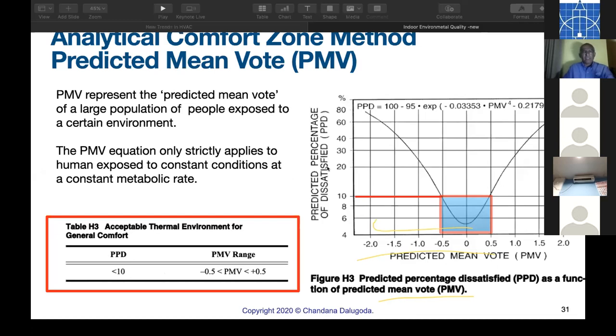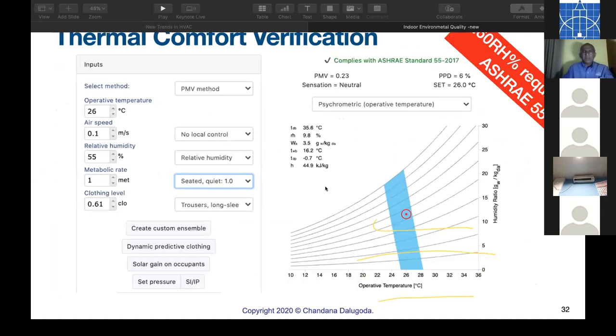By calculations, you have this automatic computer calculation program. You enter that. What do you enter? Operative temperature or dry bulb air temperature and radiant temperature, air speed, relative humidity that you are going to achieve in the air handling unit, 55. So you have to think about your return air coil temperature and the coil dew point. So 55 RH, metabolic rate, you have to see whether it is seated or running or filing, what kind of activity, and clothing. I have no time to describe all these. We can go through them in some other lecture. Then check automatically, the PMV result comes, complies with ASHRAE 55. So we can do the thermal comfort verification.